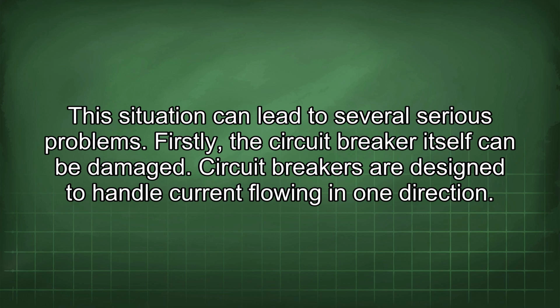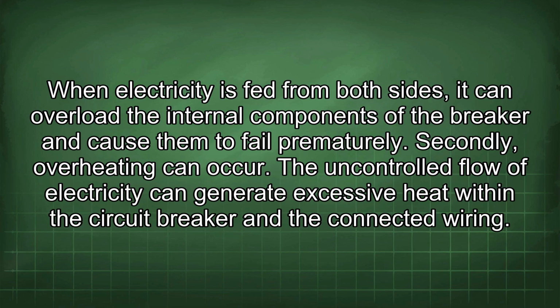Firstly, the circuit breaker itself can be damaged. Circuit breakers are designed to handle current flowing in one direction. When electricity is fed from both sides, it can overload the internal components of the breaker and cause them to fail prematurely. Secondly, overheating can occur.